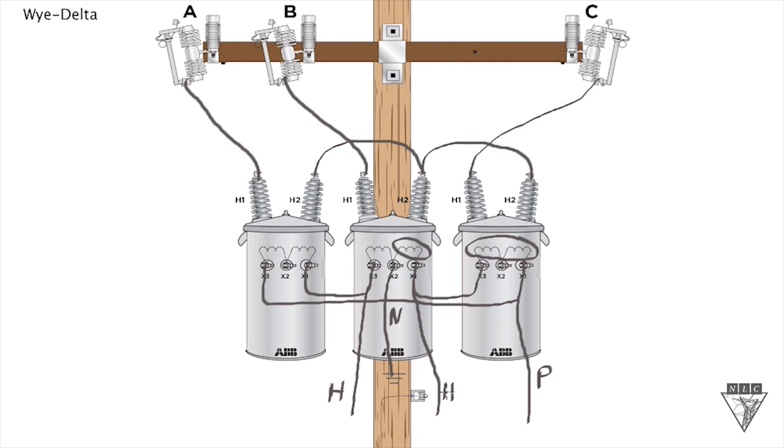Now this is important because if sometimes you can be using these connections and you need to hook up a single phase load, like to a home. Well if you're hooking up to a home you want to make sure and utilize the two hot legs and your neutral. You don't want to hook the power leg up to the single phase load because that'll pump too much voltage into the home, and that's when you can burn up electronics like computers and TVs, things of that sort. So you always want to identify your power leg and it's only utilized for the three phase power. That's the only reason why you're utilizing it.